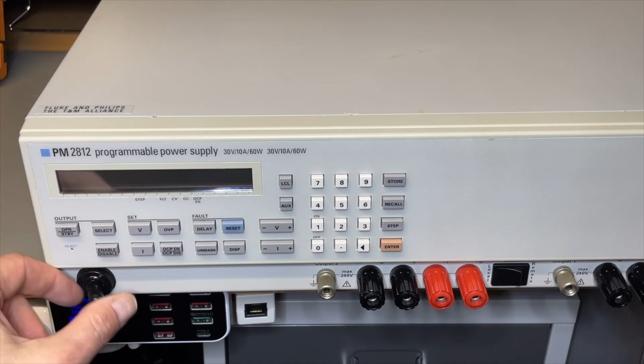Once I put it back together and cleaned it, suddenly I had an error again on one of the channels, and it was overvoltage. I noticed before that it was already very sensitive in the calibration process. Maybe that's because I'm not using the filter, and maybe because the wires are both at the bottom, it's somehow radiating or inducing into the cables, which is why it's a little sensitive. Or it's now running from the original power instead of the very clean power from the matrix power supply. So I need to look into why it sometimes shows overvoltage when I didn't set it. Hopefully I find it out.